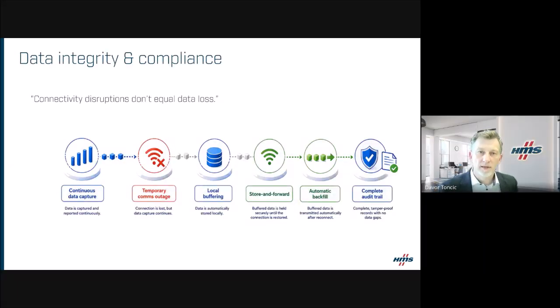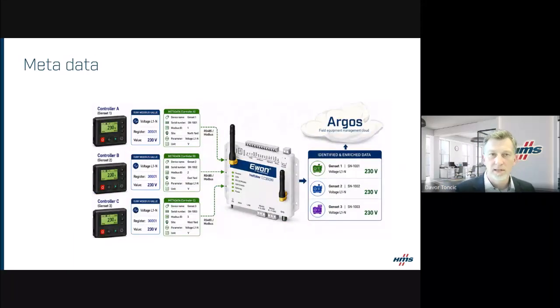One thing we wanted to highlight is the essence of metadata. When we're connecting, for instance, we have a device, a gateway, and then the same type of device connected behind it - let's say controllers, but it could be any device. If you have, for instance, 3 controllers with the same Modbus template, you need to be able to distinguish which data parameter comes from which device.